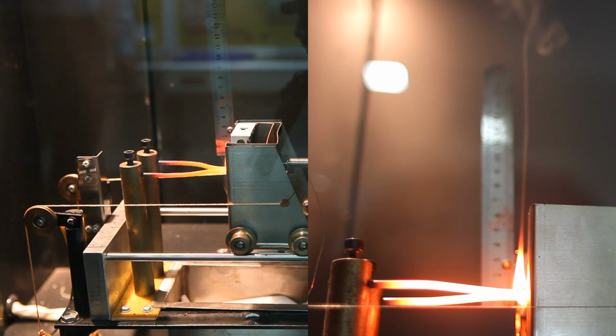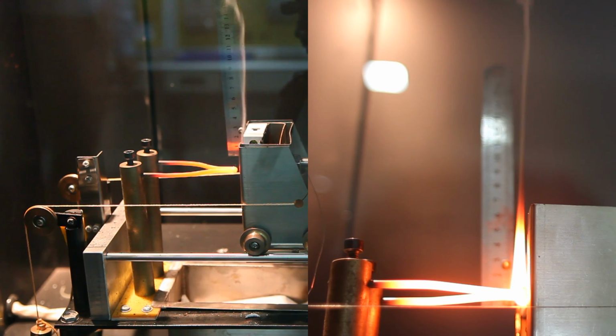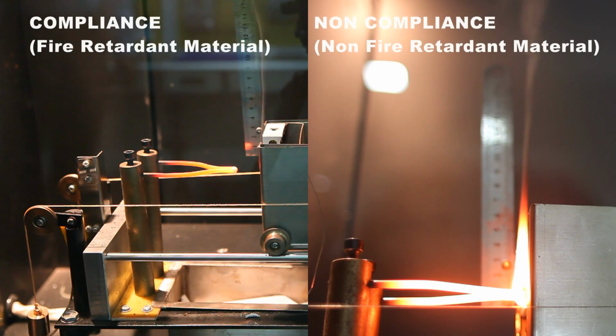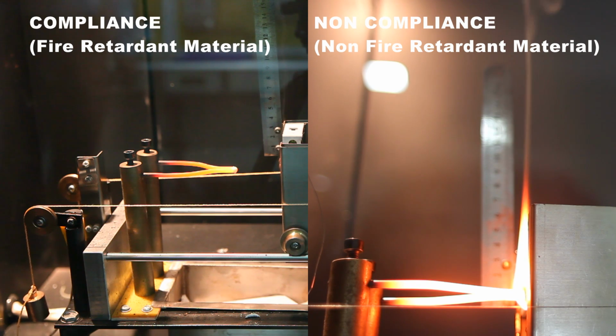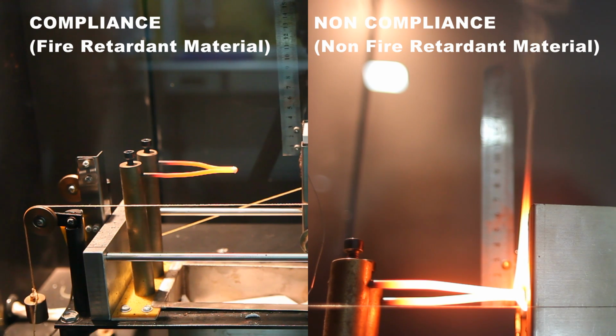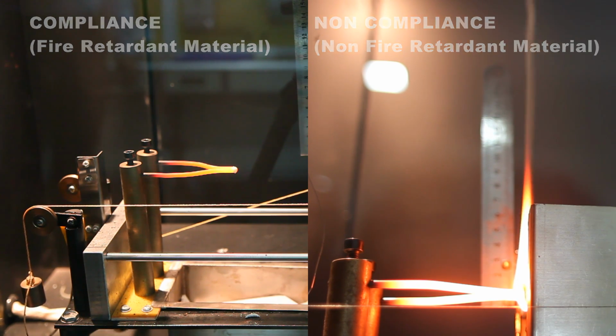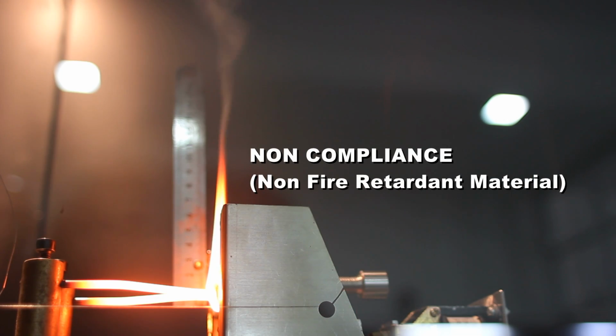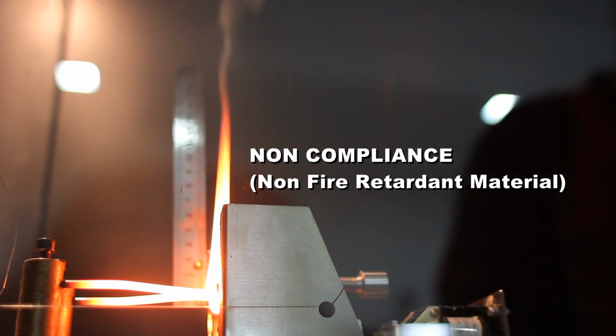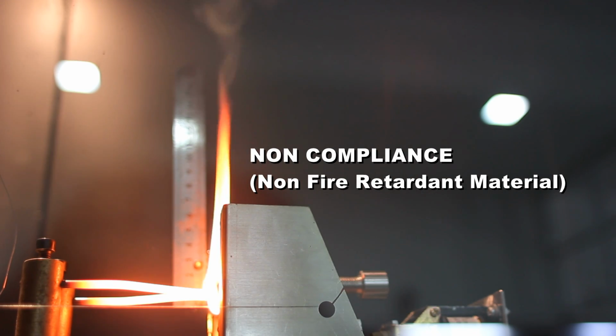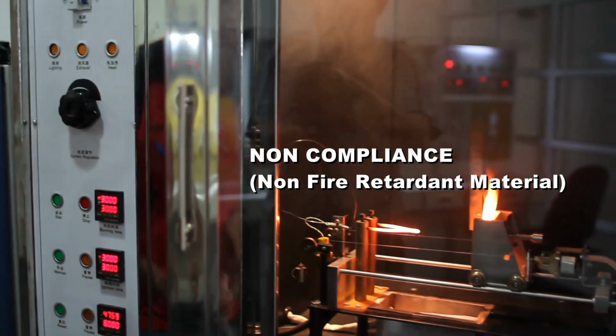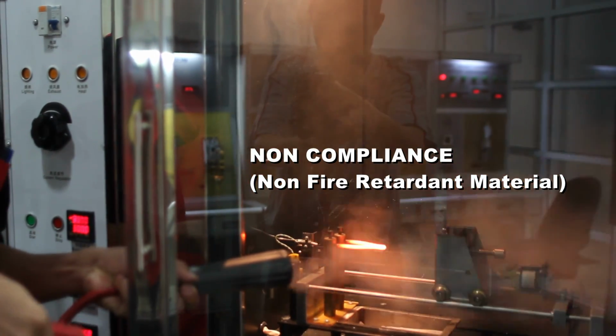During the burning duration, no droppings should burn the tissue paper or char the pine wood board placed in a recessed box positioned below the carriage. Upon withdrawal from the glow wire tip, the flame should self-extinguish in 30 seconds. This is a very important safety test to safeguard against unprecedented accidental fire hazards and risks on electrical switchgears.